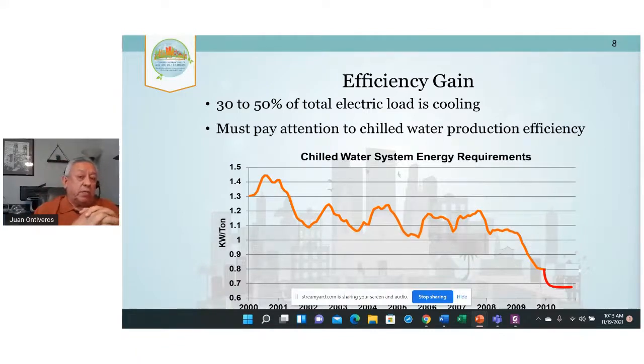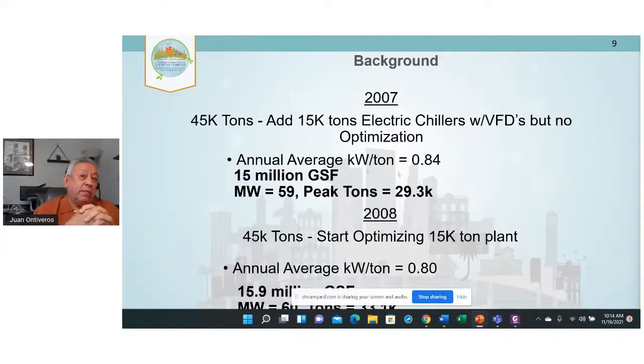And now I'm going to go a little bit into some of these strategies that we've taken. The biggest drop that occurred to us was in 2009. And this occurred when we used to use steam turbine-driven chillers to do cooling, because this is something that I inherited. They were very old, very inefficient. So when we got rid of them, converted to electrical, it really improved our efficiency down to where we were in 2010. So to give you an idea, in 2007, we had 45,000 tons of capacity because we added 15,000 tons. So we added a new cooling plant. We decided to build this new cooling plant with VFDs, but our intent was to try and optimize the cooling plant. But I wanted to run the plant a year without it and then see how the optimization improved our operation.